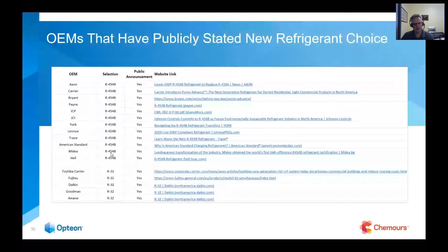Now I wanted to show you a little bit of comparison between 32, 454B and 410A. Here you can see 410A is an A1, while 32 and 454B are in the lower flammability class of A2L. There's a small amount of temperature glide in 410A and 454B, but again, the temperature glide is very small in these refrigerants. And I'm going to clarify this.